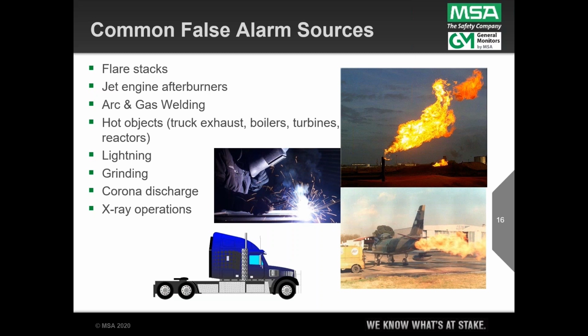Also, truck exhaust, boiler burner fronts, gas turbine combustion sections, reactors with a combustion process, or a cat cracker. They have combustion in there. The thermal signature, the black body radiation energy, is close to that of the temperature of a real fire. So in many cases, detectors are very good now, much better than they ever were at rejecting, identifying, and discriminating it, but they're not impervious. Especially if you had a combination of things going on, like a hot turbine or a hot reactor signature along with some lightning or a grinding nearby, now you've got this combination platter of IR energy and UV energy, and you're setting the stage for things to happen.